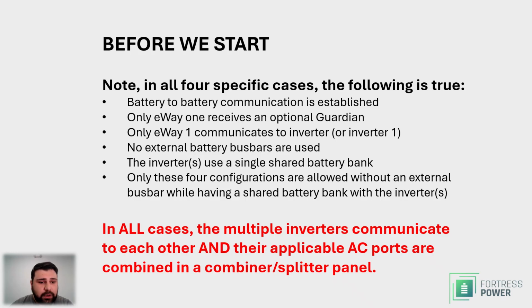So in all 4 cases, battery-to-battery communication is established. That is a requirement that you must have closed-loop communication between the batteries and the inverters. If there is a circumstance in which that cannot be achieved and you need open-loop communication, that must only happen with tech support's approval and assistance.